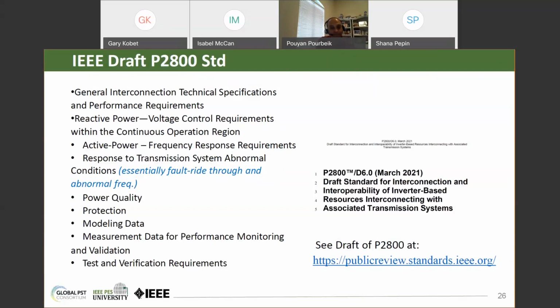The standard covers all these things that we just discussed, that the NERC task force had identified as gaps: to define reactive VAR control requirements, to define minimum requirements for active power frequency response, for fault ride-through, for power quality, protection. It talks about the kind of models that are available, what some of the measurement and data requirements are for validating those models, and starts to touch on test and verification requirements, although those will need to be more fleshed out in this proposed second standard, P2800.2.